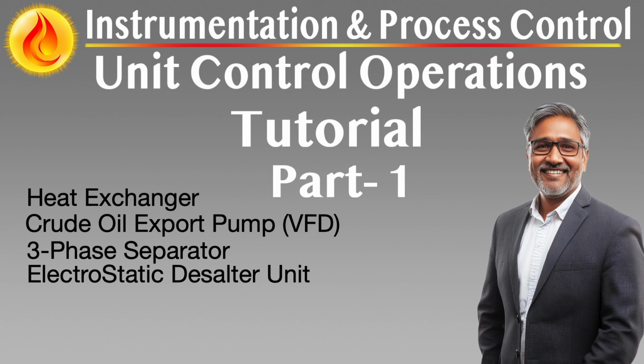Pressure control remains central to gas outlet management. Vented gas must meet pressure specifications for flare systems, gas compressors, or reinjection lines. PID-based pressure control loops are enhanced by surge protection logic and anti-slug algorithms, particularly in fields with inconsistent wellhead pressure or high gas-oil ratios. Some systems incorporate anticipatory logic based on upstream production data or real-time modeling, allowing pressure control valves, PCVs, or VFD-controlled compressors to react ahead of surges or drops, thereby preventing trips or flaring events.